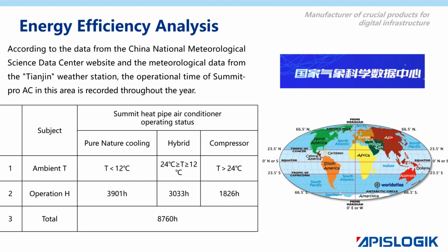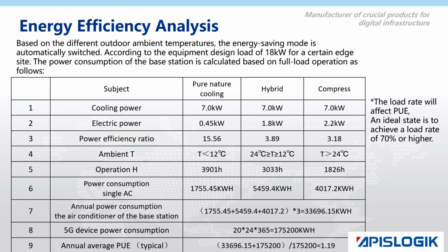In tropical regions like Singapore, where the average temperature ranges from 23 to 31 degrees Celsius throughout the year, the system would mostly operate in full compressor mode. However, with good sealing and duct design, it is still possible to effectively reduce energy consumption. In the Tianjin region of China, based on the mentioned temperatures, for a business customer with an 18 kilowatts load, the average annual PUE can reach 1.19. This represents a reduction in energy consumption by 30% to 50% compared to typical micro data centers.